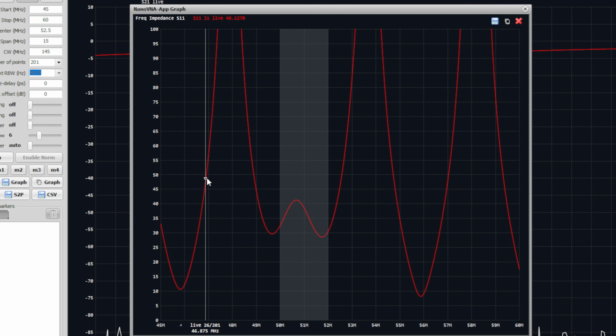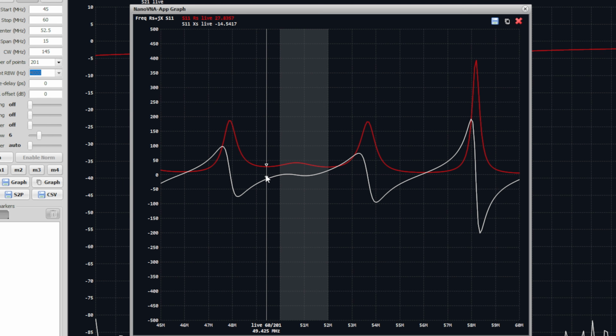We can also look at impedance. So we can see here that the impedance jumps up and down. We're looking at the impedance at 50.7 megahertz, which is right there. We're sitting on 40 ohms or so, or 42 ohms, I think it was. We can also look at the complex impedance, with the resistance and also the reactance. So at 50.7 megahertz, there it is. We've got our white line, which is our reactance, and our red line, which is our resistance.